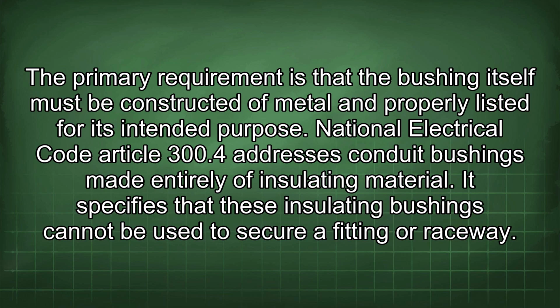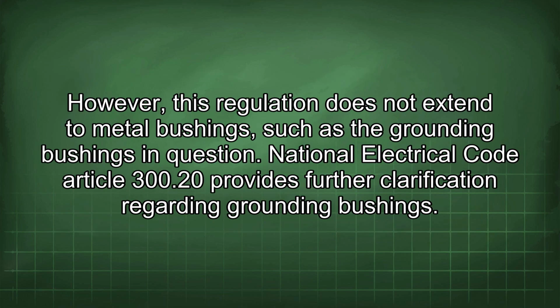National Electrical Code Article 300.4 addresses conduit bushings made entirely of insulating material. It specifies that these insulating bushings cannot be used to secure a fitting or raceway. However, this regulation does not extend to metal bushings such as the grounding bushings in question.